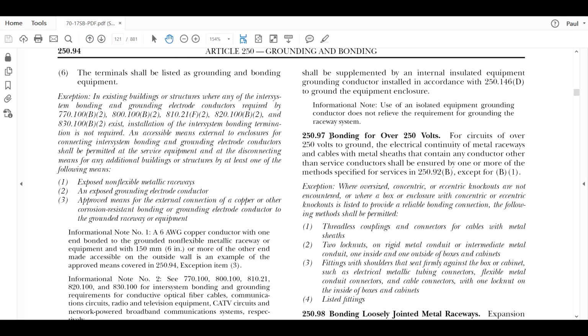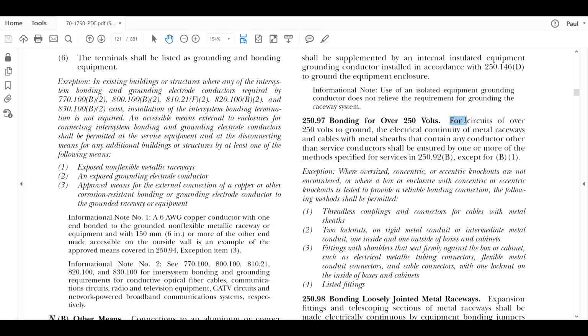All right, so bonding for over 250 volts. Let's read it. Real important. It says, for circuits of over 250 volts to ground, and of course a 277/480 would be, a 480 would be, all that goodies. A 208/120 would not, so don't worry about that. It says the electrical continuity of metal raceways, which that FMC is, and cables with metallic sheathing, that'd be like an MC, that contain any conductor other than service conductors, and obviously these aren't service conductors we're talking about, shall be ensured by one or more of the following methods specified for services in 250.92(B).